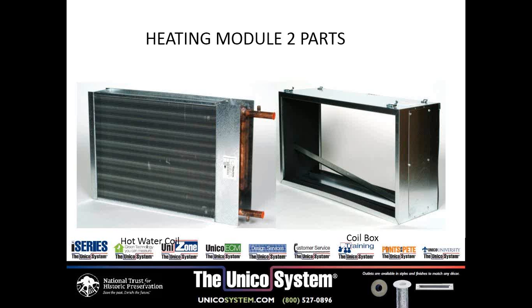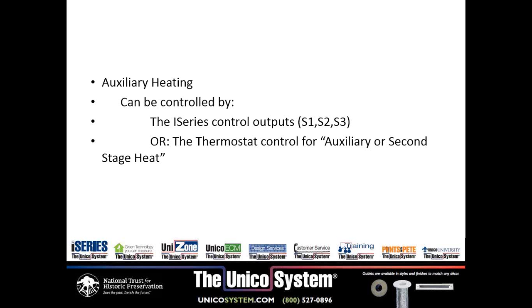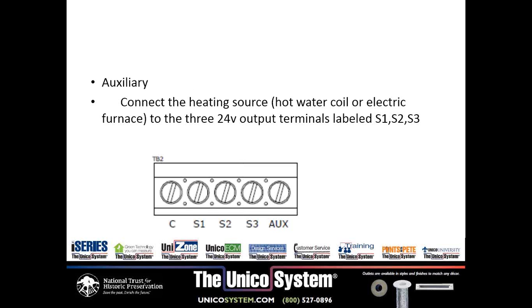So what we have with this is a need to provide either hot water, which we see right here as auxiliary or emergency heat, or an electric furnace. Your choice is up to you and what your climatic conditions are, what the cost of fuel in your area is, etc. But the heating module is essentially the same as an automobile. When your car turns on heating, you have hot water going through a coil that air passes through with a fan, and that delivers hot air to the different parts of the room. With the I-Series, we can control this with either outputs labeled S1, S2, S3, or you can just get a 2-stage thermostat. Either way will turn on the emergency heat below a predetermined temperature. This is how we connect it, very simple. We can use this with hot water or an electric furnace.